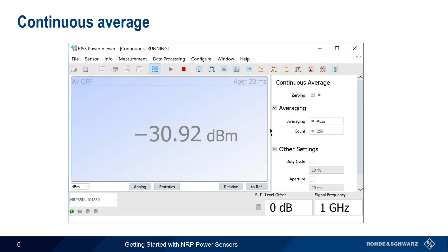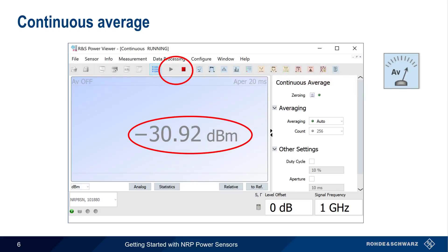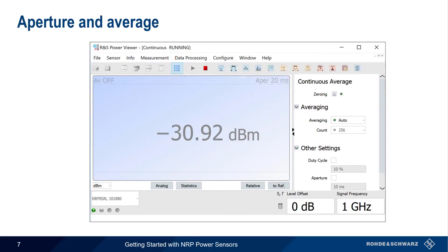In this presentation, we'll be showing how to make measurements in Continuous Average mode, which is the most common mode used when measuring power. Measurements can be started or stopped using the play and stop buttons, and the power level is displayed continuously while running. Note that we can also change the measurement units to watts, volts, etc. The two parameters which most influence power measurements are aperture — how long each measurement takes — and average count, or how many measurements we make before reporting the results. These are shown in the measurement results window.